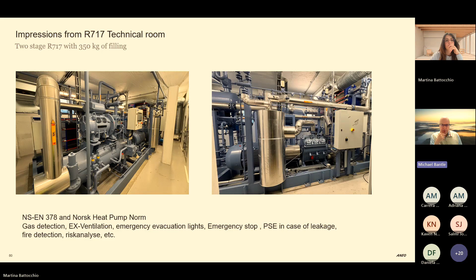Next slide, please. Here we see some pictures from the technical room. We basically have two rooms. In the first room, you see the ammonia heat pump system, where we take in the energy at 20-30 degrees on the left side and then start compressing it up. In the picture on the top right, to the left, you see the heat exchanger where we start to generate steam by evaporating water while condensing ammonia.